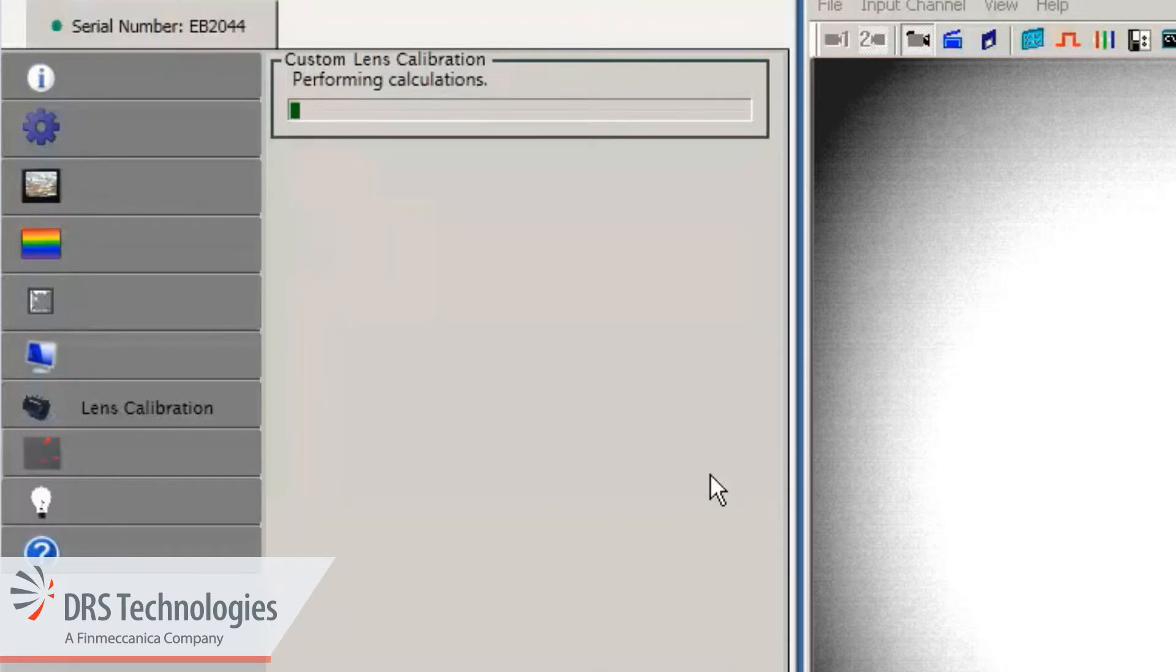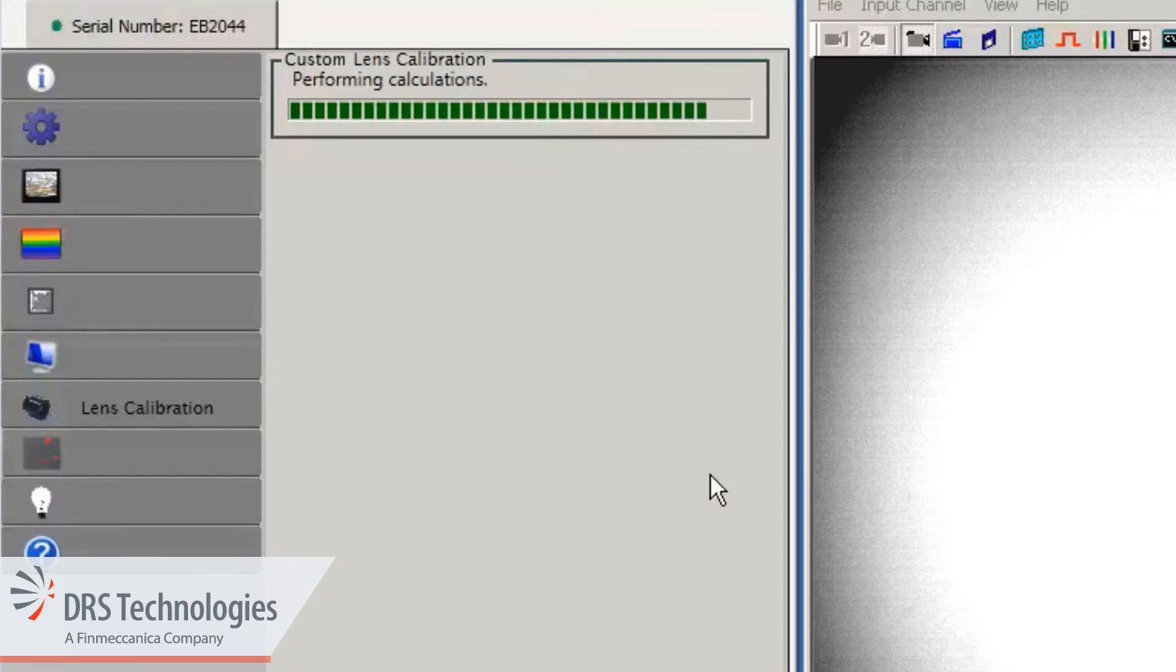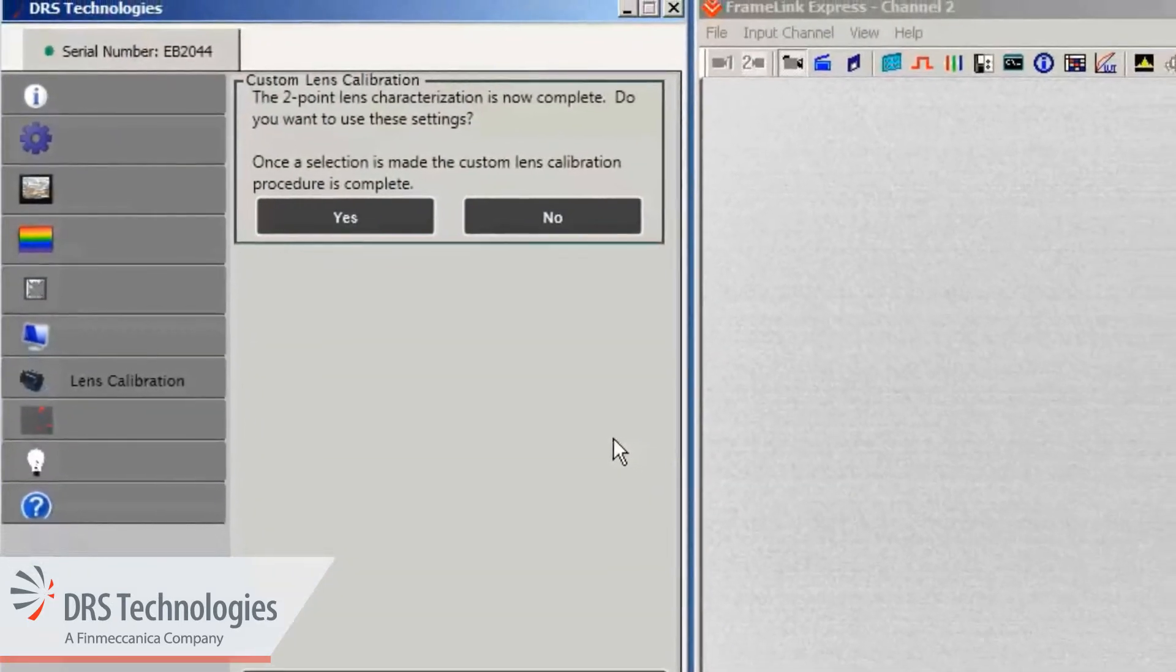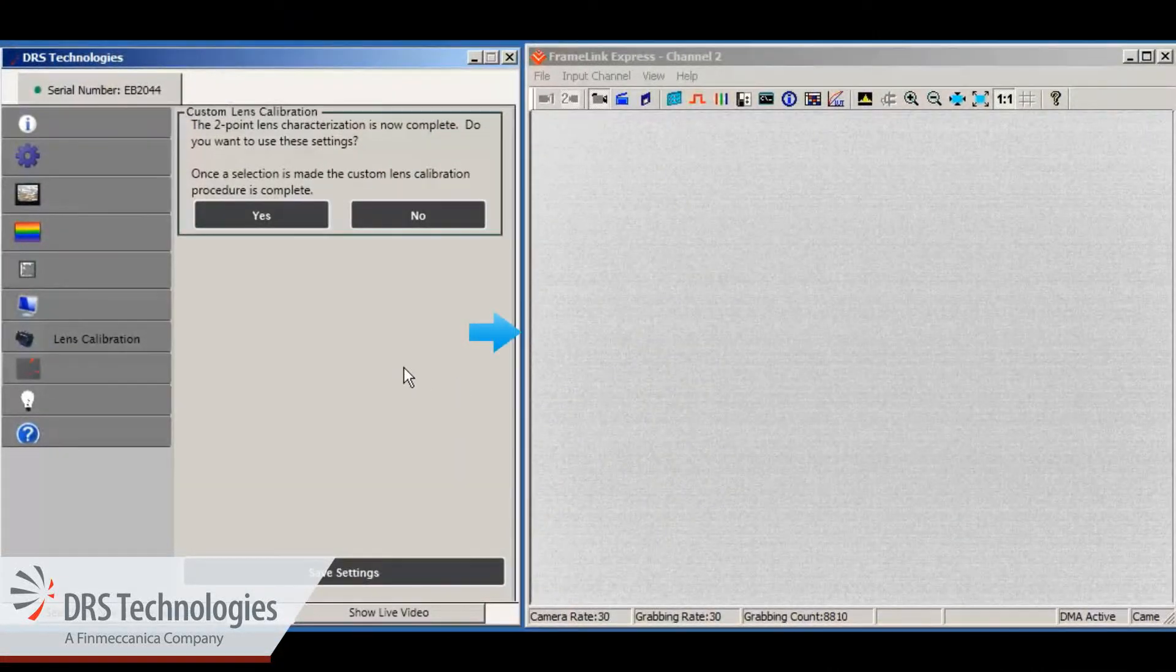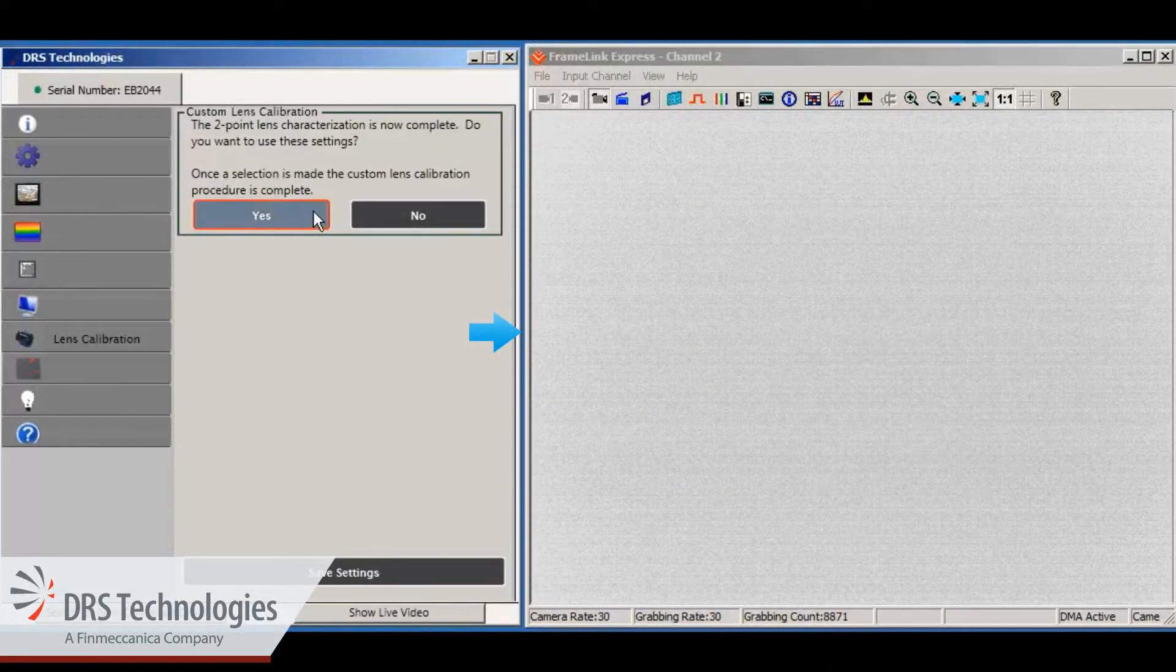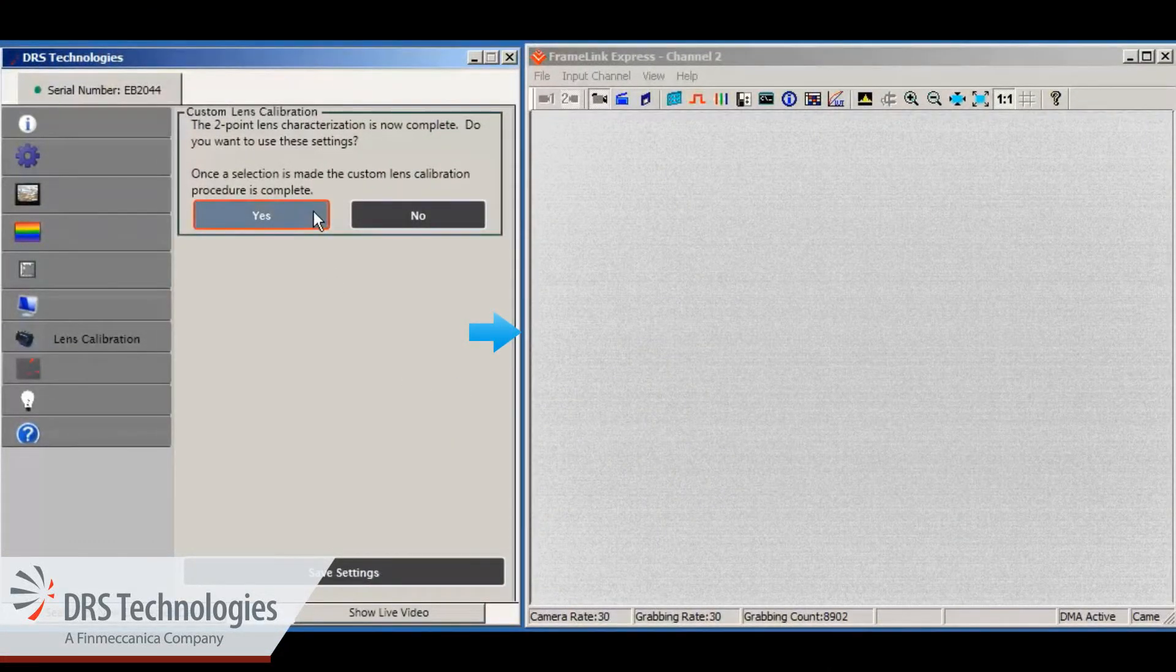The camera now calculates the gain and offset data. Once this is complete, the software will prompt you to save the new settings. A uniform image on the monitor indicates a successful calibration.